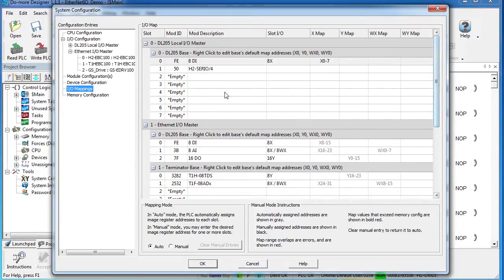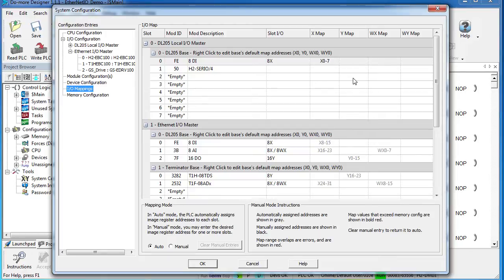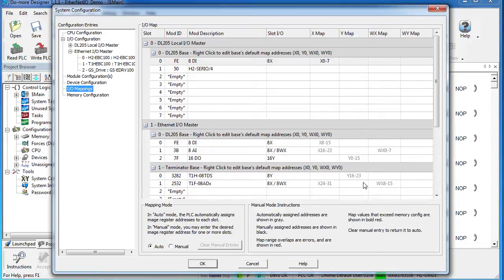The only problem with this is: what if I add another I.O. module back in the base down here? Suppose it's got some inputs and some outputs. Well, if Auto Mapping is selected, then those will be assigned the next addresses, and it will bump all these up to the next available address. And that can really mess up your ladder code.